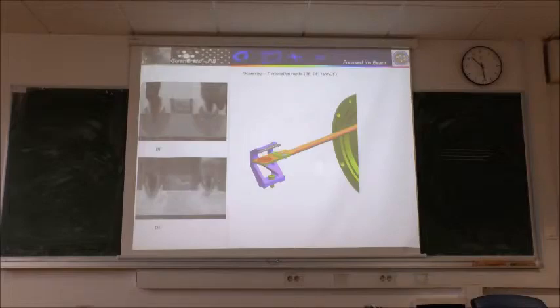Okay, in this microscope we have another possibility, the so-called scanning transmission mode. Very thin samples, like those prepared for the transmission electron microscope, go on a special sample holder. This is the path of the electrons, and this detector is retractable. So when we need it, we put it in. When we do not need it, we take it out.